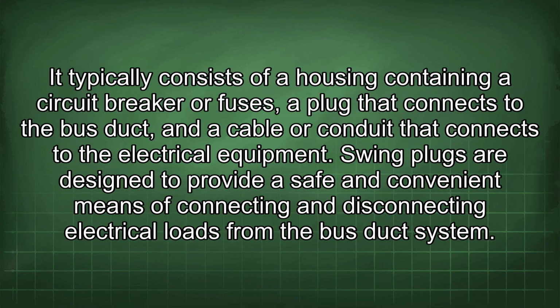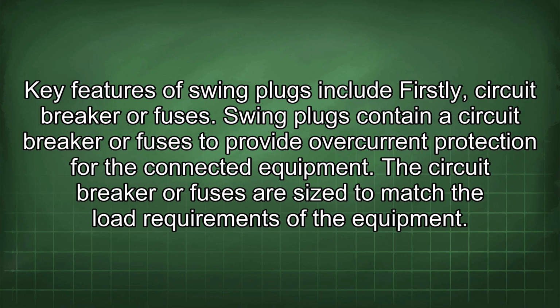It typically consists of a housing containing a circuit breaker or fuses, a plug that connects to the bus duct, and a cable or conduit that connects to the electrical equipment. Swing plugs are designed to provide a safe and convenient means of connecting and disconnecting electrical loads from the bus duct system. Key features of swing plugs include, firstly, circuit breaker or fuses. Swing plugs contain a circuit breaker or fuses to provide overcurrent protection for the connected equipment. The circuit breaker or fuses are sized to match the load requirements of the equipment.